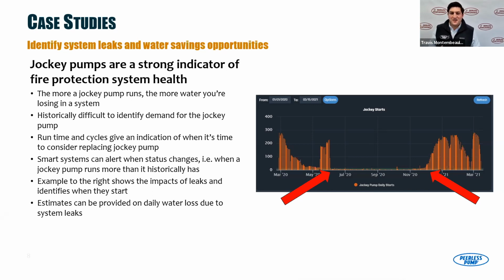So you bring in environmental and sustainability goals here. Yeah, it's a big factory and maybe 1 million gallons of water isn't a ton in the scheme of things in terms of how much they're using, but it's not insignificant. And it also points to a better, tighter fire protection system. Using the Peerless factory as an example, we put a new loop in within our facility a couple of years ago, and now it makes for a really boring system to look at in FireConnect, because our jockey pump runs like twice a day, maybe. So it's a really tight system, but at the time it could run 100 times a day, no problem. These old loops just tend to leak, especially the valves around the loops.